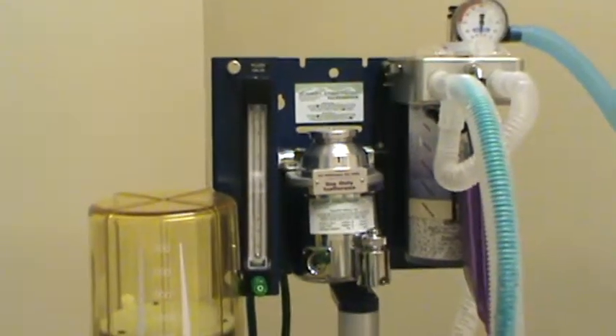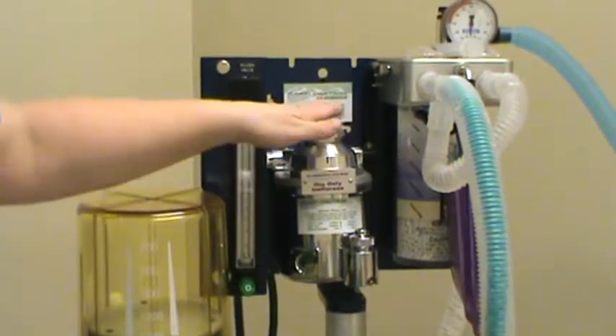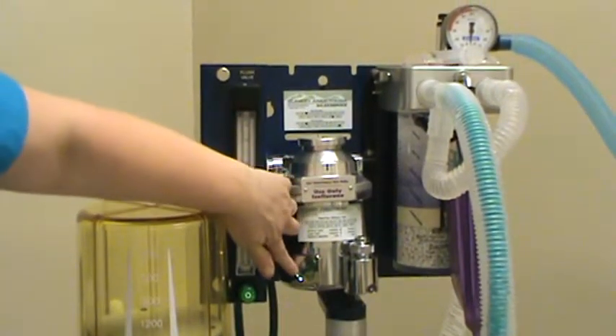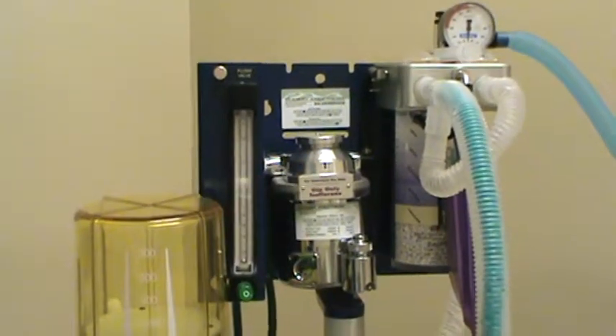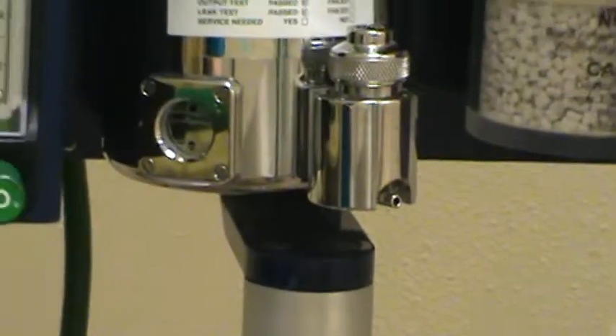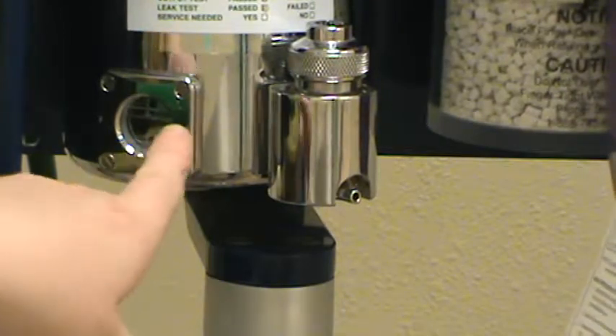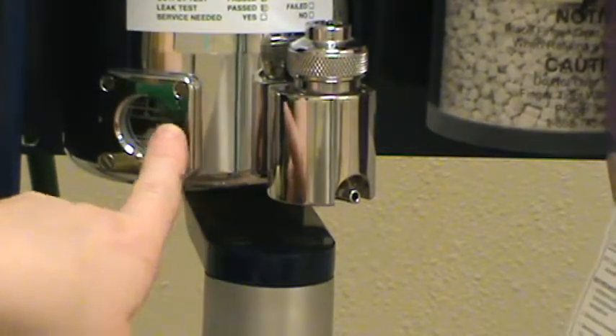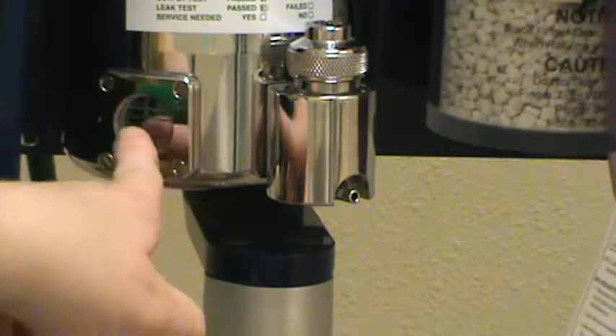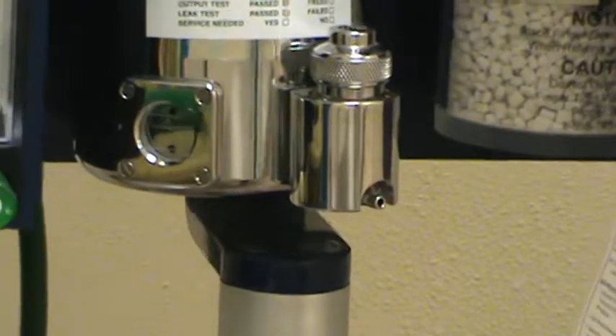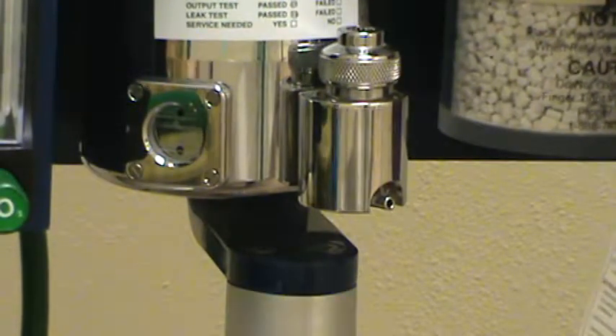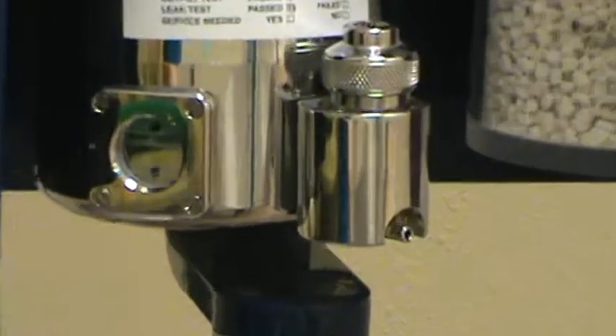Second thing we're going to do is verify that our vaporizer has enough gas anesthetic in it. I'm going to show you here. This is the level right here where our gas anesthetic is. It has a little more than half full, so we have plenty of gas anesthetic in our machine.